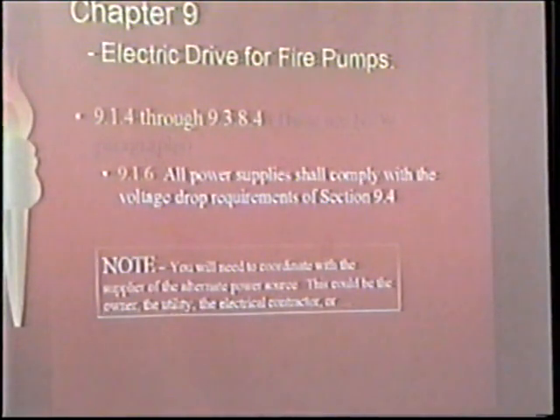We may get there and find out that we can't support the fire pump motor. What's the symptom of that happening? What will happen is the contactor will fail to pull in. It'll sound like a gun going off multiple times. The contactor pulls in, the arc flash of it hitting the contacts drives it back open, and then it goes back closed, and it does that a few times. And you'll hear it. If you ever hear it, you'll know what you heard, because there's no mistake in it.